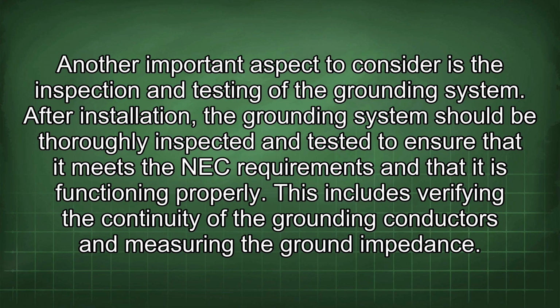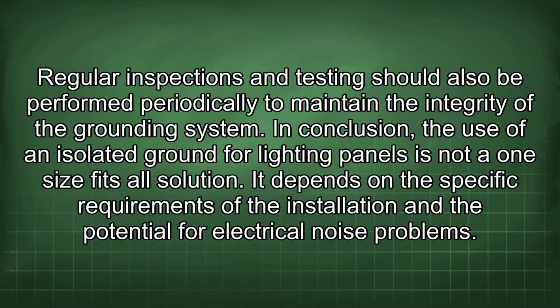Another important aspect to consider is the inspection and testing of the grounding system. After installation, the grounding system should be thoroughly inspected and tested to ensure that it meets the NEC requirements and that it is functioning properly. This includes verifying the continuity of the grounding conductors and measuring the ground impedance. Regular inspections and testing should also be performed periodically to maintain the integrity of the grounding system. In conclusion, the use of an isolated ground for lighting panels is not a one-size-fits-all solution.